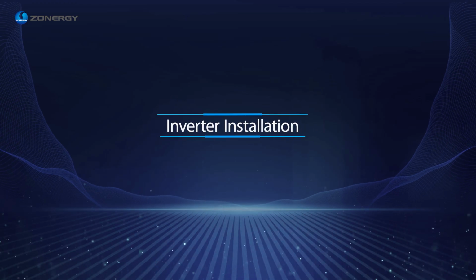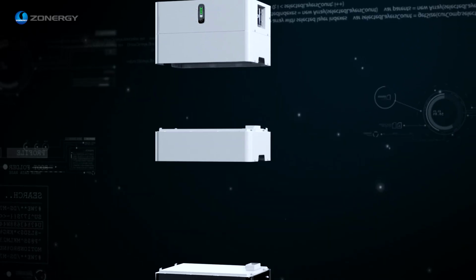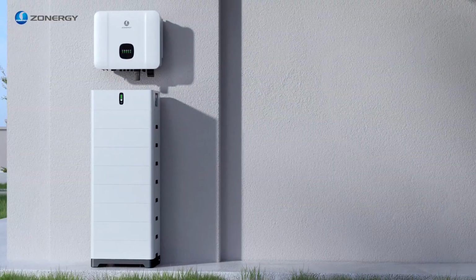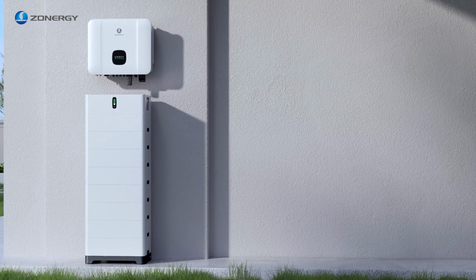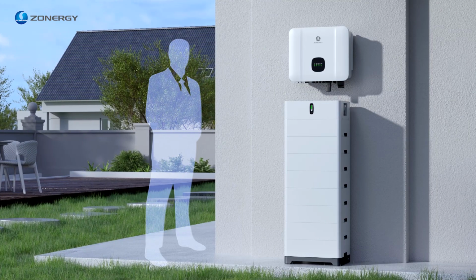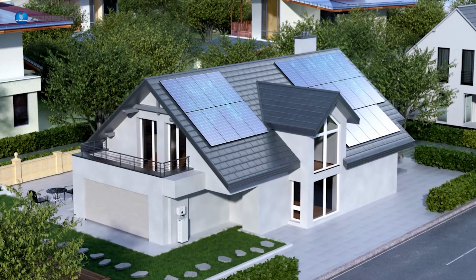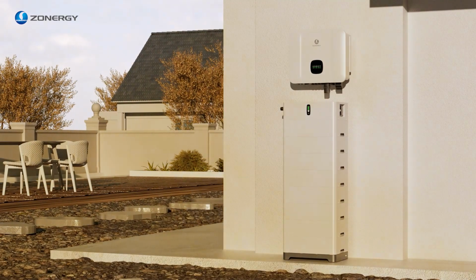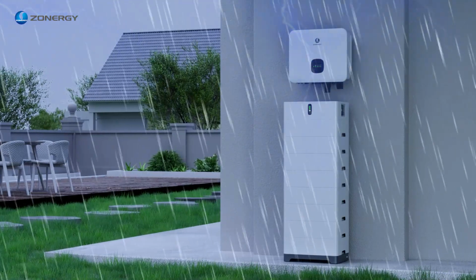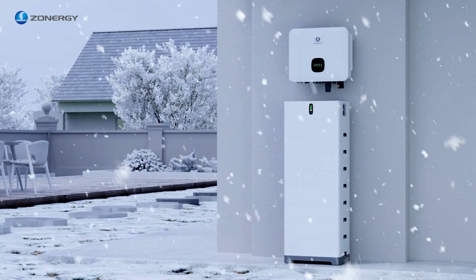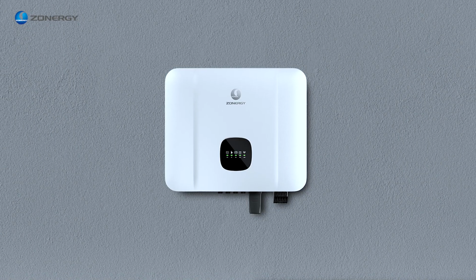Chapter 3 Inverter Installation. The wall of the installation must be strong and able to withstand its weight for a long time. Install the inverter at eye height in order to facilitate future maintenance work. It needs to have a shelter, IP66 protection class, and can be installed indoors and outdoors. Ensure that the inverter has enough clearance.